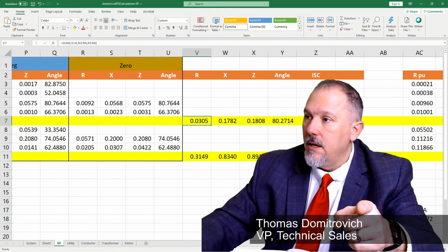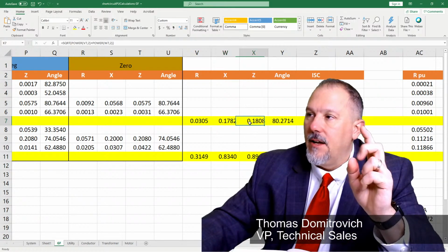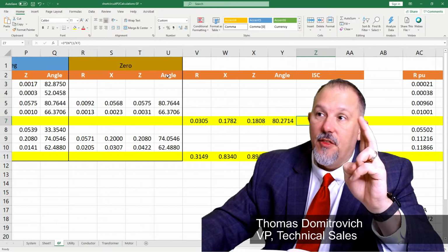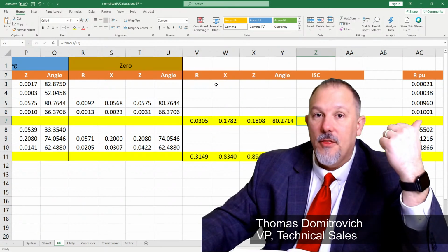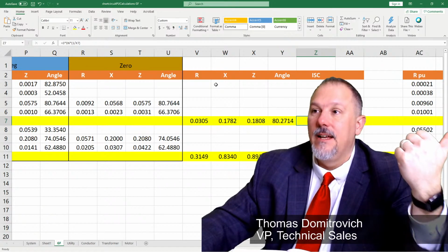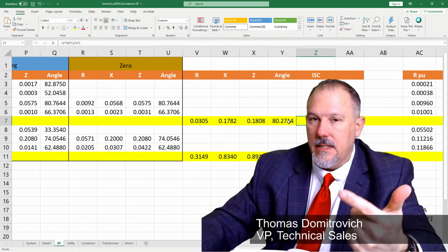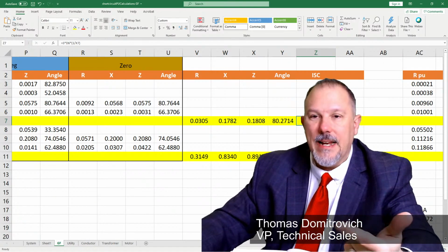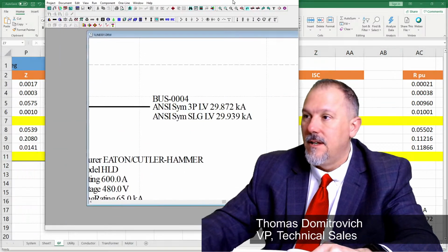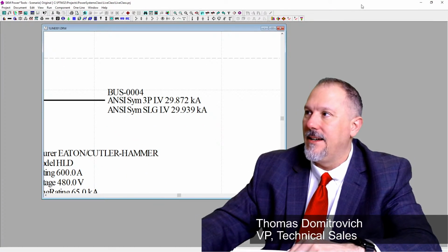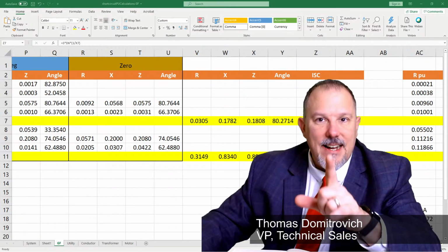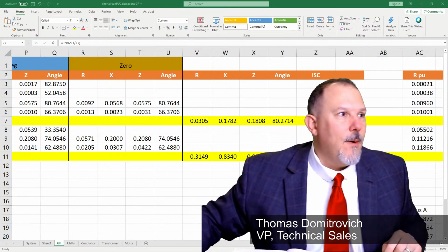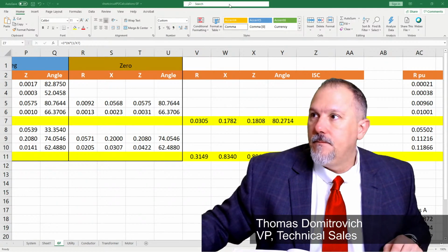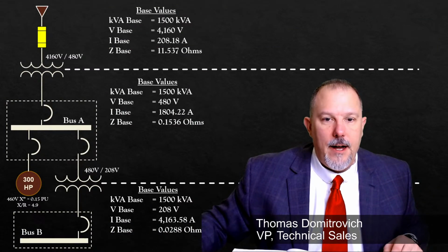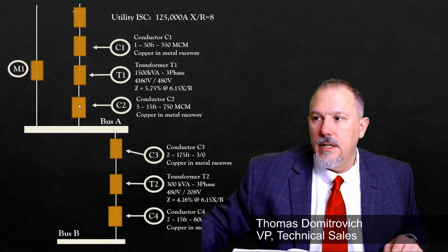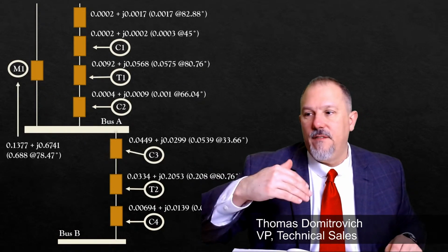So I have an equivalent R, an equivalent X, a Z, and an angle. And then I do my 3 times my base current divided by this impedance. And I come up with 29,939. So that's how it's done. Now, how do I calculate the ground fault current at bus B?